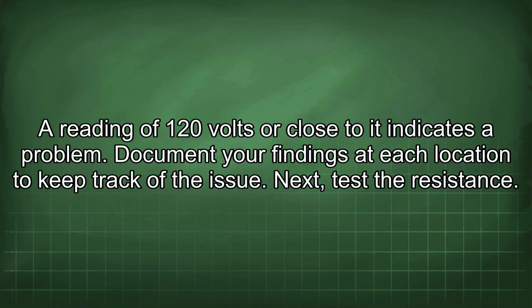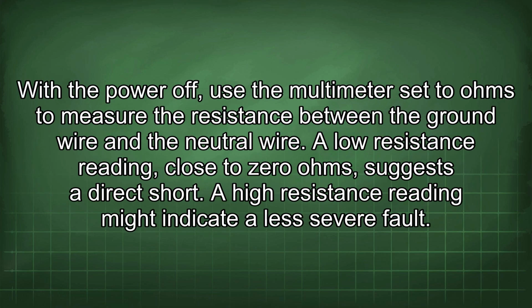Next, test the resistance. With the power off, use the multimeter set to ohms to measure the resistance between the ground wire and the neutral wire. A low resistance reading, close to 0 ohms, suggests a direct short. A high resistance reading might indicate a less severe fault.